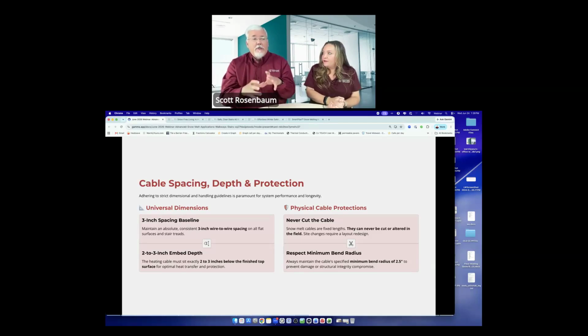Yeah. And the National Electric Code says if you have something that heats, it cannot go in that tube. So it's very, very important to keep that in mind. You're protecting that splice from heating and cooling too fast and failing on you.